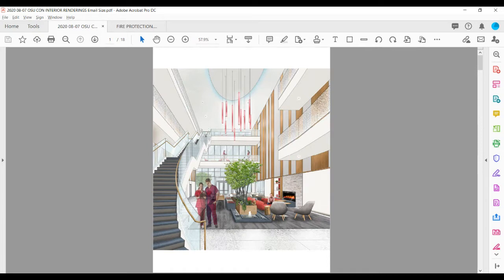No, Paula, that is a VESDA type air sampling smoke detection system, a UL listed air sampling smoke detection system. There are sampling ports up on the ceiling at spacing that in our case here is less than 30 by 30, and air samples back through those sampling ports, pulling back through a tubular network to the detector in the unit itself. So it actually pulls air and samples the air back into a sampling chamber for the detection application. It's UL listed and actually considered to be an advanced detection system from that standpoint.